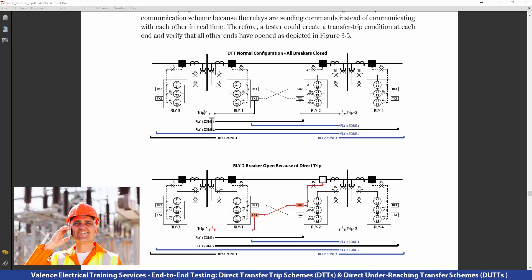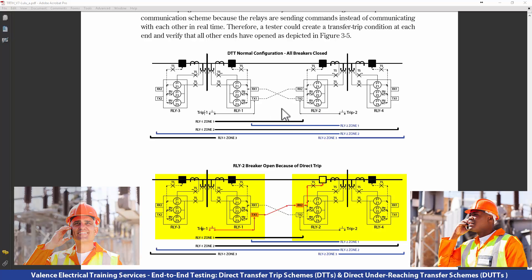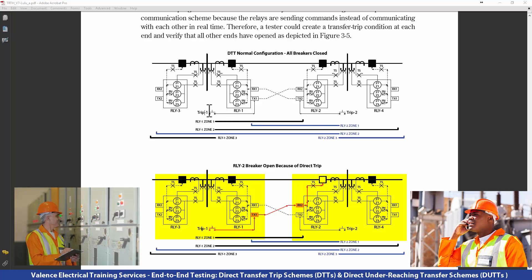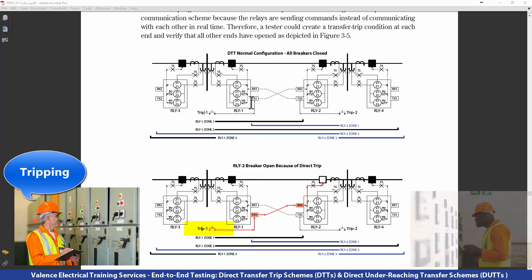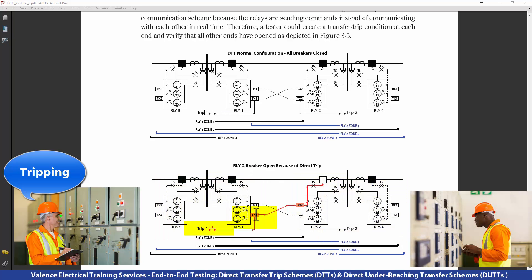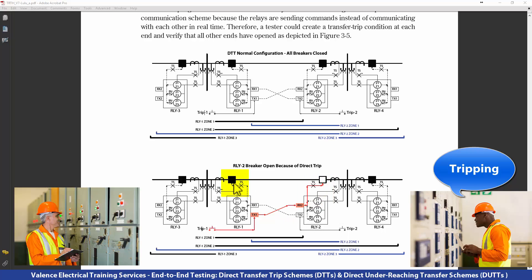Put one person at Relay 1, another at Relay 2, get on your cell phones, and have person 1 push the trip button. The trip button will go to the transmit of Relay 1, then send a signal to Relay 2. Relay 2 will receive that signal and open the breaker. Person 2 pushes their button, then the reverse should happen, and breaker 1 should open.